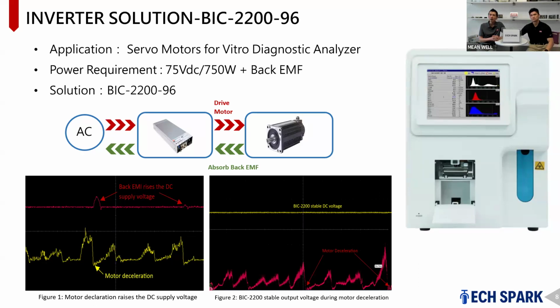So we were looking for a solution. The solution here is that the customer either has to get a regeneration clamp circuit to damp down the back EMF, or, as we discussed and suggested, the BIC 2200, which is able to absorb the back EMF energy from the motor. How it does this is that it has an automatic inverting mode that can dump all the energy back to the grid.